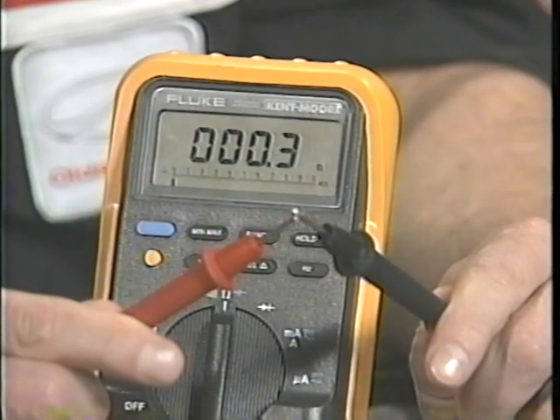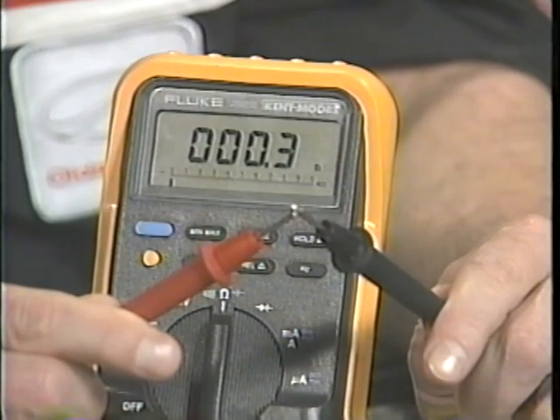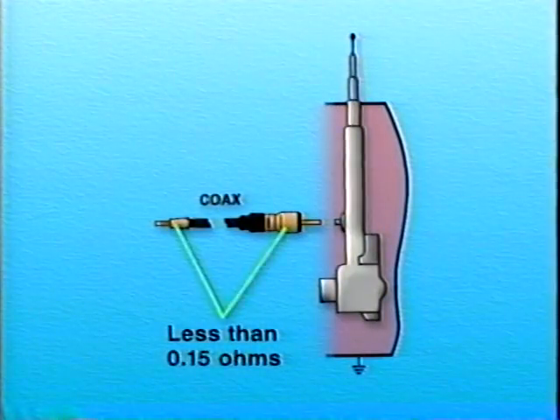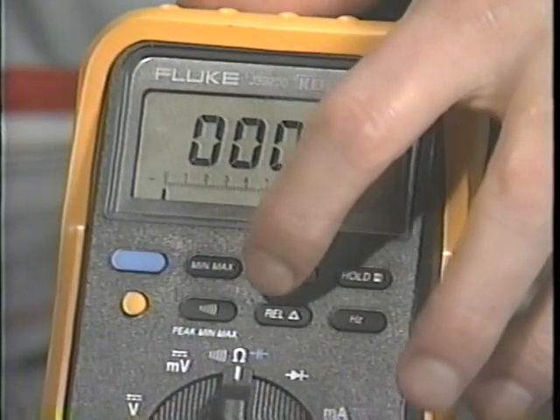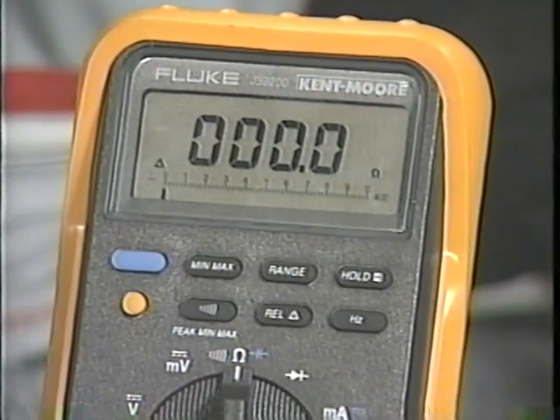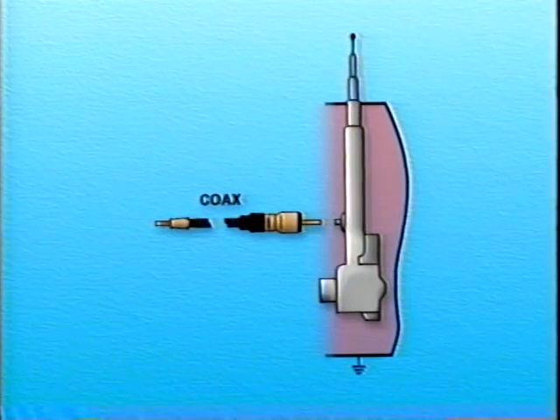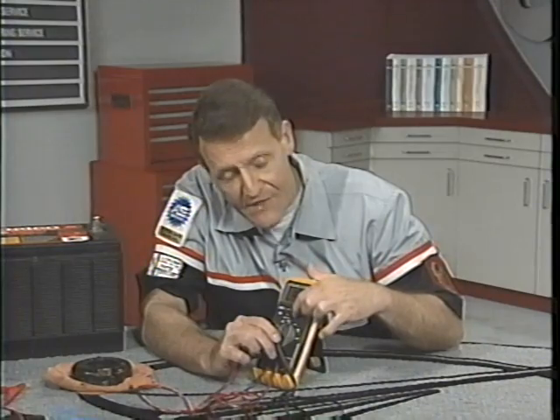Then touch the probes together and hold them there. This reading is between 0.2 and 0.3 ohms. That's nearly twice what's allowed in the cable to be checked. So we press relative delta, and the meter accepts that value as the baseline, as 0. Now our measurements would show the resistance of only the cable or antenna being checked. You hold the relative delta button down to leave the function.